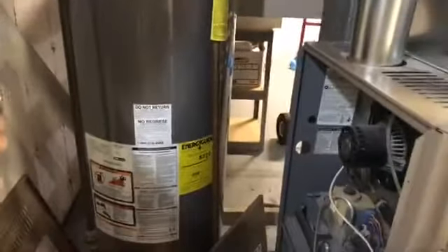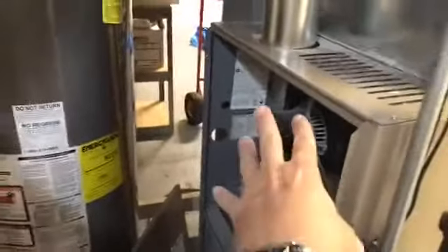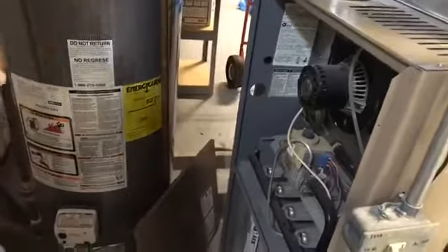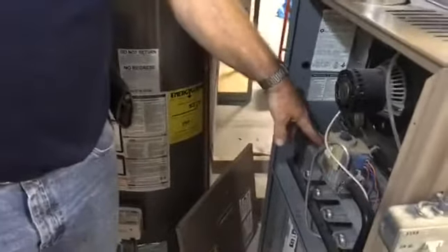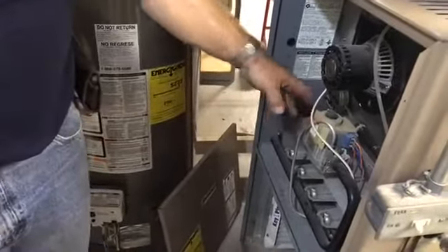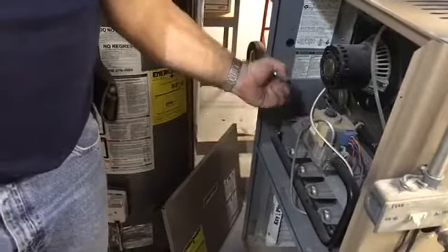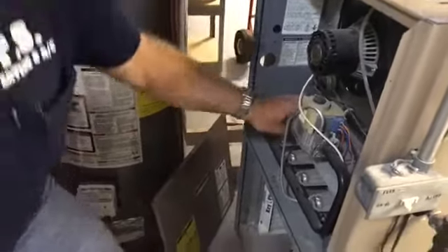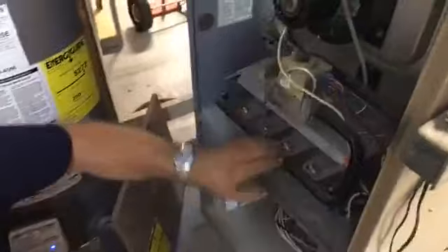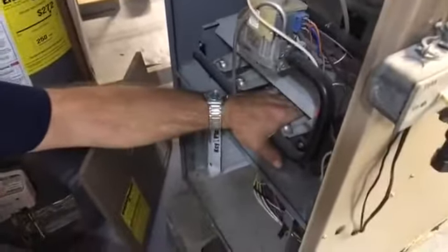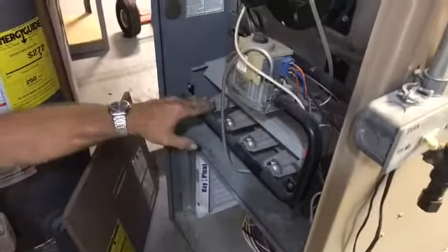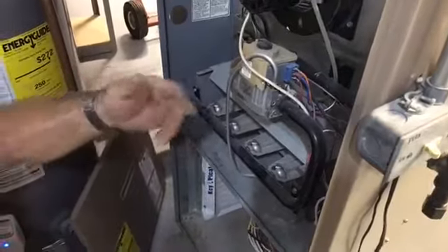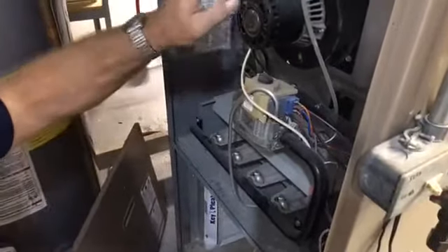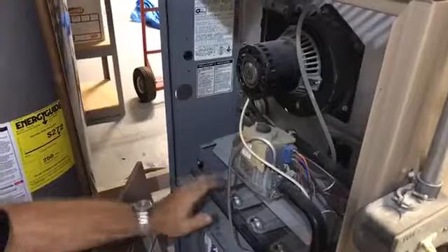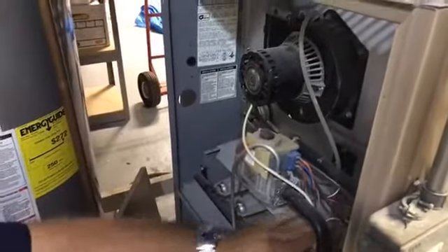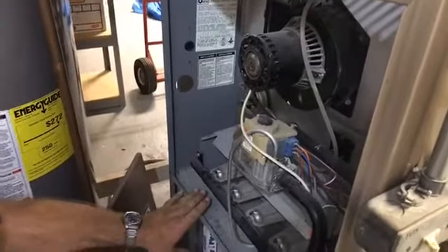On a normal inspection, I know you check fan operation and... We check ignition. This one does not have a pilot. It's got a hot surface igniter on the bottom of the pilot tube. So it does light a pilot, but it does that automatically. Then it lights the burners, and then we check sequence of operation. We have pressure switches and draft motors and safeties for the flame and high limit protection. We check all of those and make sure they're working.